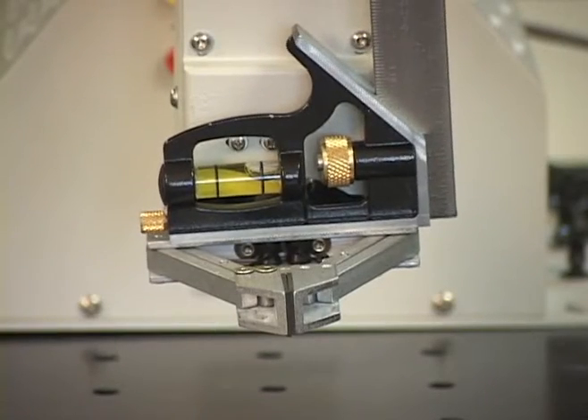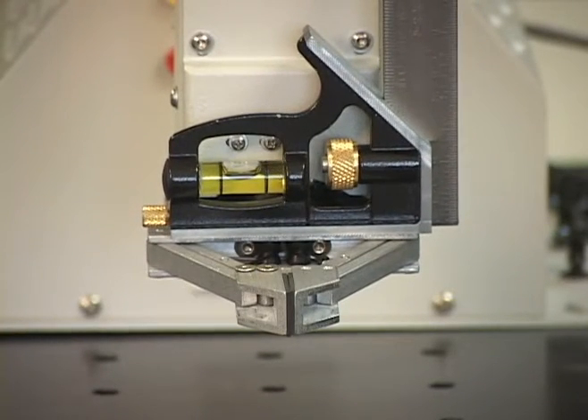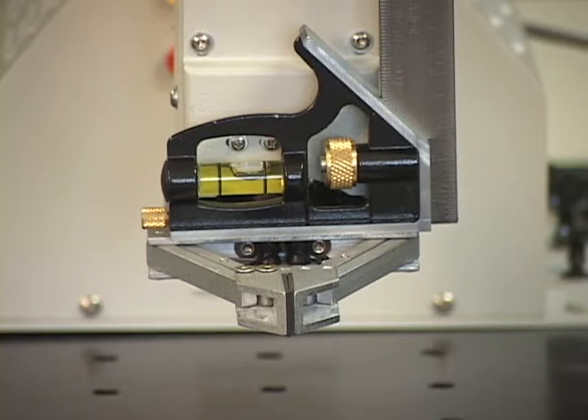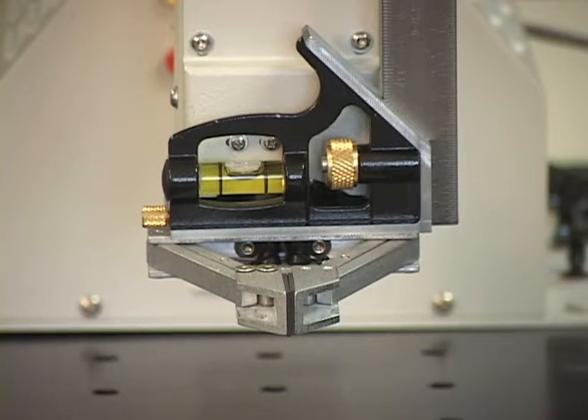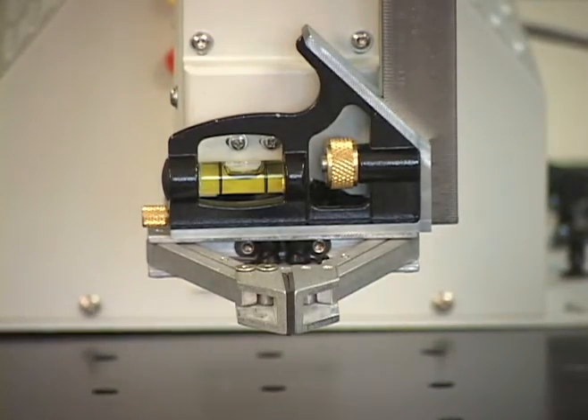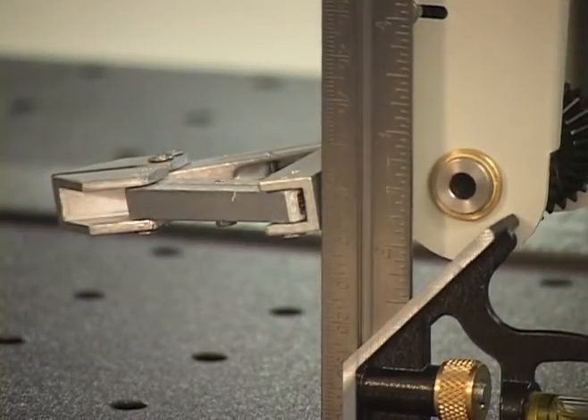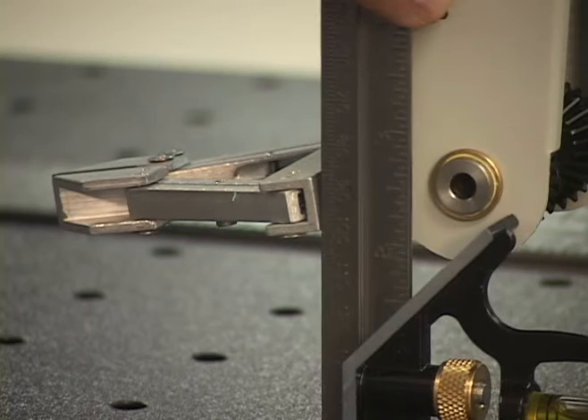Calibrate the wrist roll articulation by positioning the combination square onto the gripper assembly. Move the roll articulation until the square bubble is level. Note: if the roll articulation is moved, you will have to perform this step again.